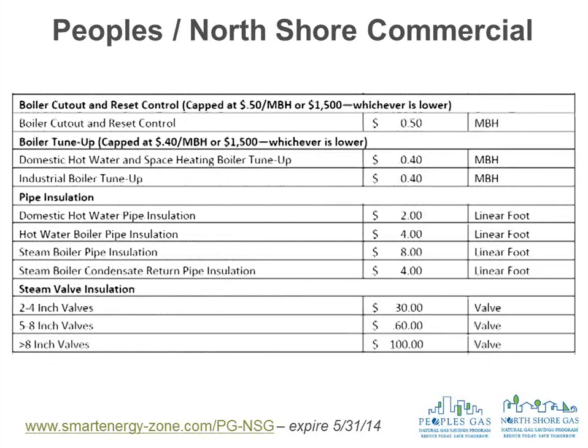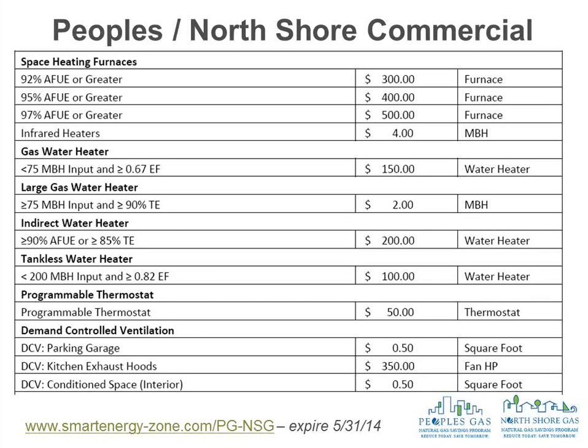Condensing unit heaters, steam boilers, outside air reset controls added on to an existing boiler, 50 cents per MBH, just like the NICOR stuff was. Boiler tune-ups, 40 cents per MBH, up to a maximum of $1,500 per boiler. Pipe insulation, anywhere from $2 to $8, depending on how hot the pipe is that you're insulating. The hotter it is, the more it can waste, so hotter pipe like steam gets a bigger rebate. Steam valve insulation. Furnaces used commercially, infrared heaters. In that case, it's $4 per MBH. So on the NICOR side, it was $700 per infrared heater. On the Peoples North Shore side, it's $4 per MBH of the burner of the infrared heater.